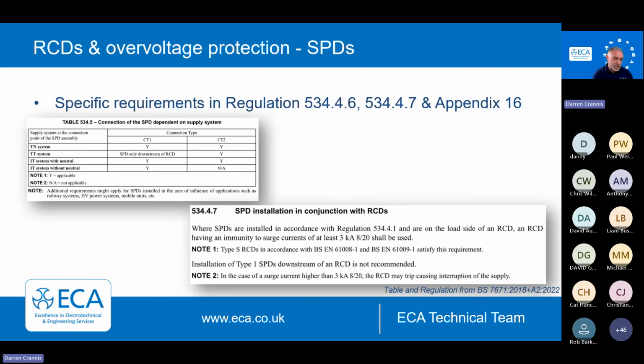I'm not going to go into too much detail on this slide right now, because we talk about where RCDs and SPDs are in conjunction with each other, but importantly, it's a difference in what we call CT1 and CT2. We'll come on to this later on, but it's about selecting. If you've got an RCD, you have to make sure you select the right SPD to avoid nuisance tripping.